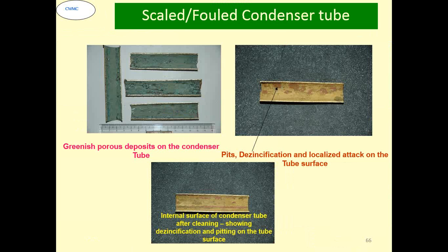What you see here is the greenish product. This is a typical fouling that has been caused by the treatment chemicals, in this case ferrous sulfate, which is dosed as a corrosion inhibitor in a copper-based system in seawater. Now, on the same tube, if you see below, severe corrosion has taken place. You can also see localized attack on the tube. Because of this, the tube starts puncturing and you start getting condenser leaks.